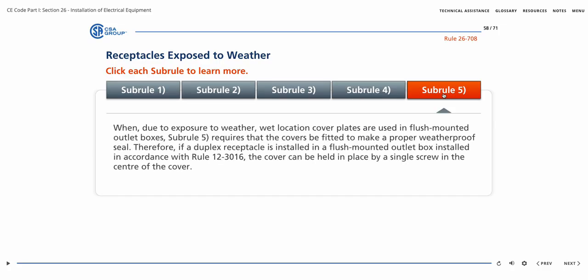When, due to exposure to weather, wet location cover plates are used in flush-mounted outlet boxes, Subrule 5 requires that the covers be fitted to make a proper weatherproof seal. Therefore, if a duplex receptacle is installed in a flush-mounted outlet box installed in accordance with Rule 12-3016, the cover can be held in place by a single screw in the center of the cover.